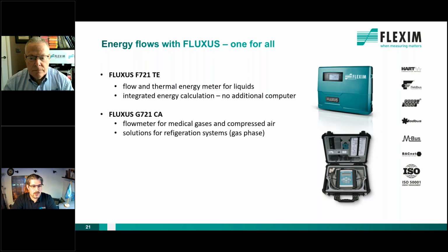Of course, we already learned about the G721CA. The CA stands for compressed air, but this is also feasible for medical gases and compressed air, including, of course, medical air, and also much more sophisticated solutions like metering gaseous ammonia, for example, in a refrigeration system. So if you have, for example, an ammonia compressor, which you can use for creating deep temperatures for a refrigeration process, we also have solutions to get you the information about your compressor output in your cooling system.